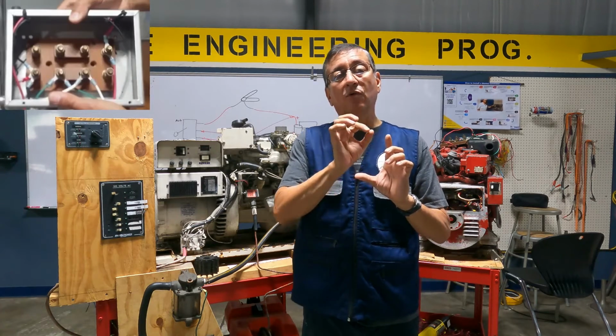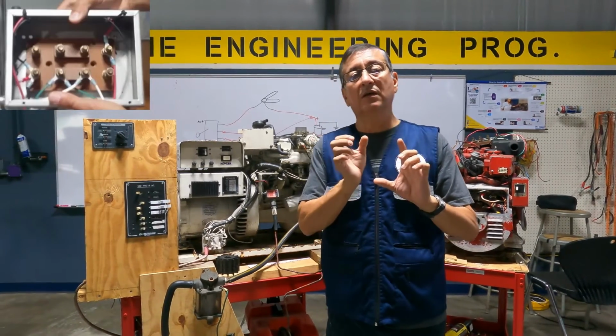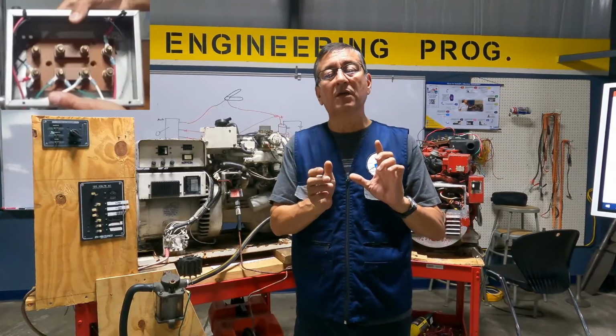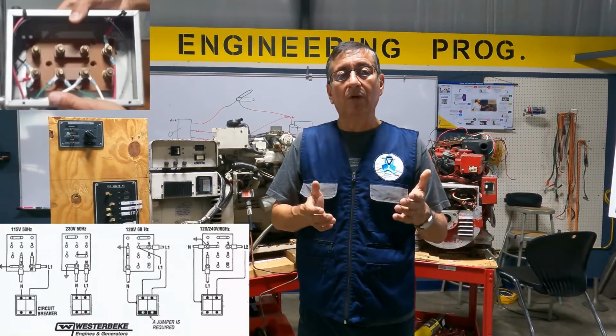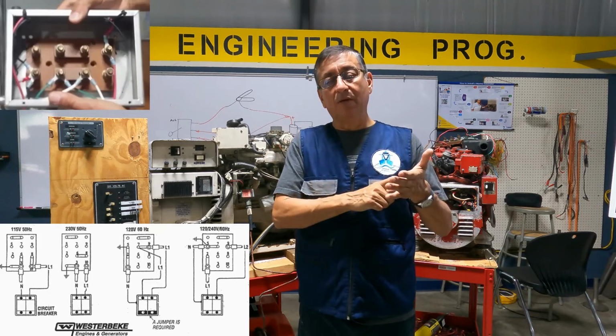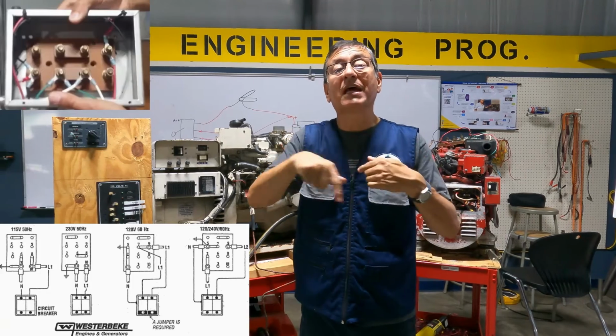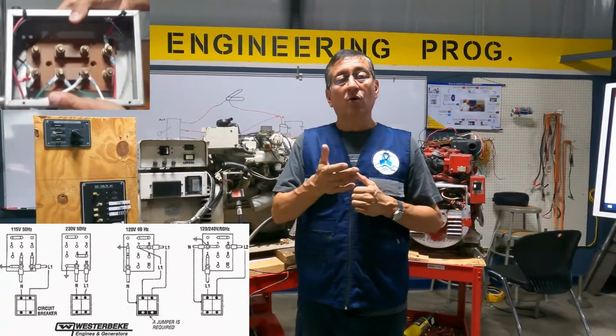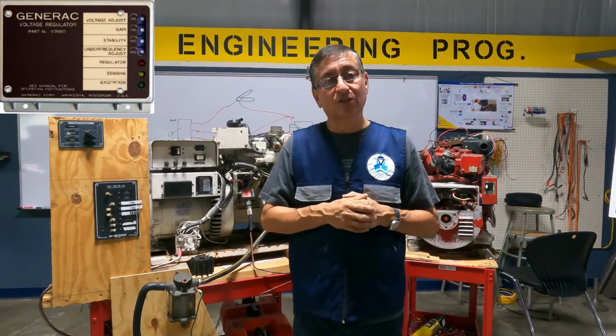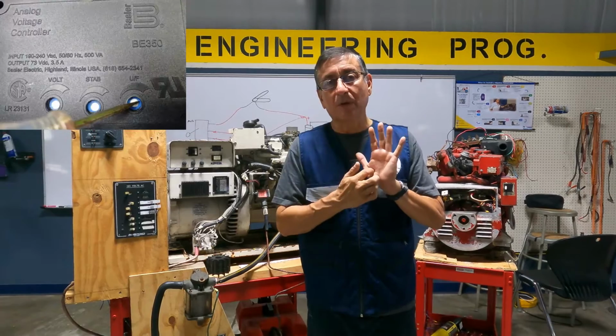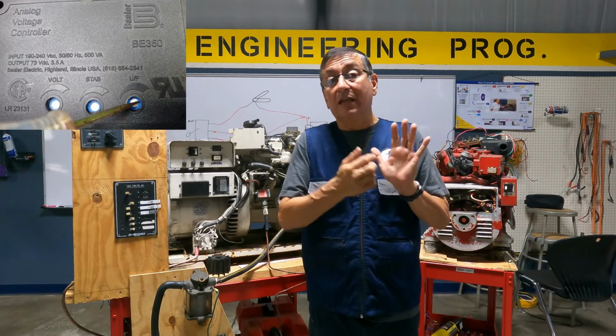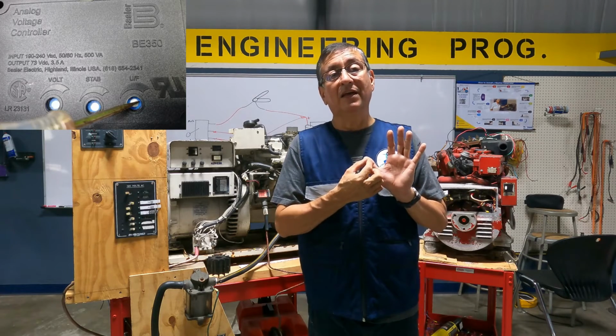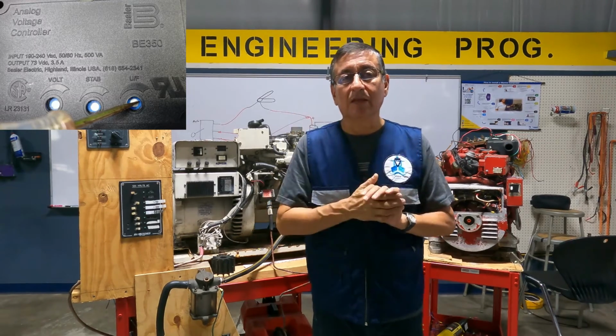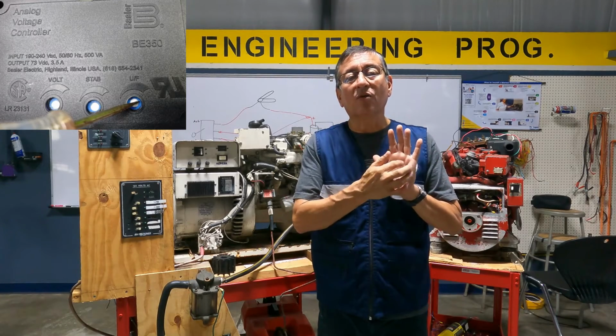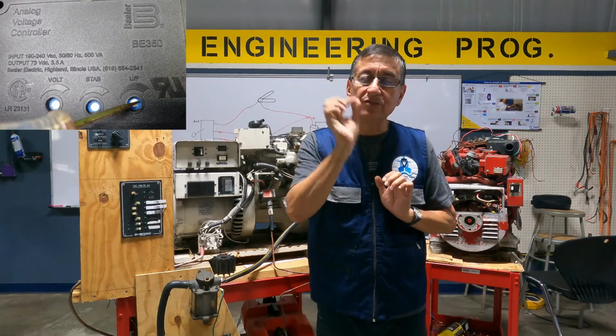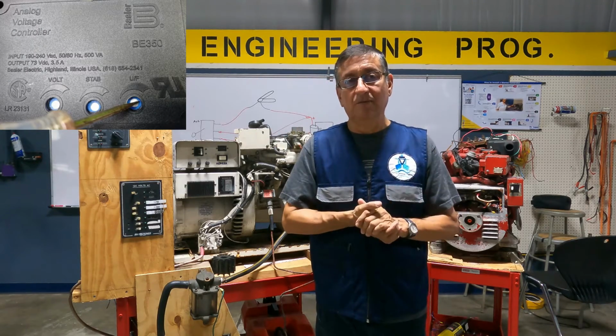where the configuration for single phase 60 Hz, double phase European power 50 Hertz is. How is it configured? Check the manual and verify that the power, according to the manual, is configured properly on that board. Understand the board, the AC board. Also, verify where the voltage regulator is located. Where are the three spots, you remember, for gain, stabilization, voltage, and in some voltage regulators, frequency adjustment for fine adjustment. Verify where each of those spots is located, and verify if you have the small flat screwdriver to adjust in case it is necessary.